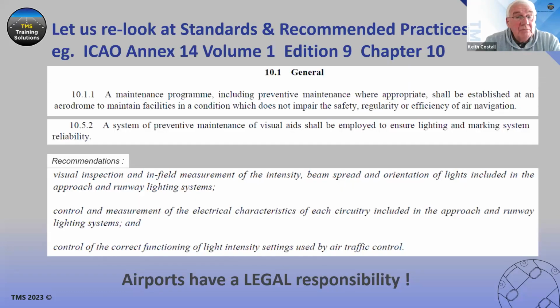So looking at standards, what do they say, and do we on airports globally implement these requirements? There's a maintenance program that shall be employed as a preventive maintenance program, and there are three key issues recommended to achieve that: visual inspection and in-field measurement of intensity and beam spread; the control, switching it on and off at different intensity levels; and looking at electrical characteristics like the quality of the electrical circuit. Airports have a legal responsibility in this respect.